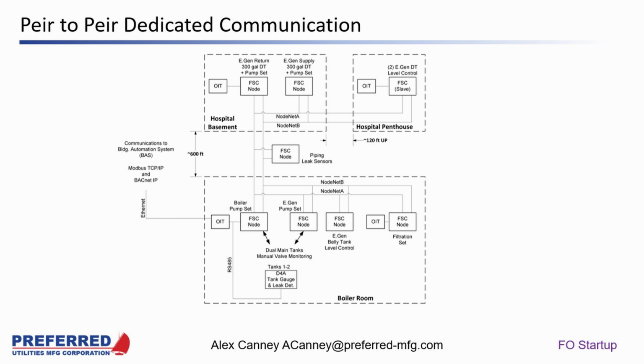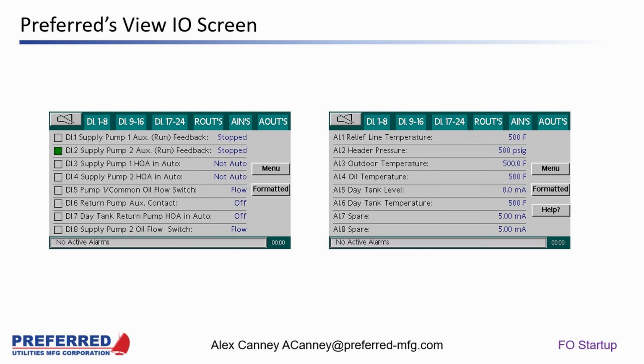Last question: is preferred view IO optional or standard on preferred systems? This is a system where you can look at your voltages and amperages. Yeah, that's standard on everything. For all of our on-off discretes on an FSC, you'll see a little box that'll be green or light gray, and you'll get your milliamps for our analogs on every system that has a touchscreen. Our standard is a 4-inch touchscreen. For larger systems, we'll often do a 10-inch touchscreen or have it go back to a command center, so you can see a full system overview, which is very helpful.